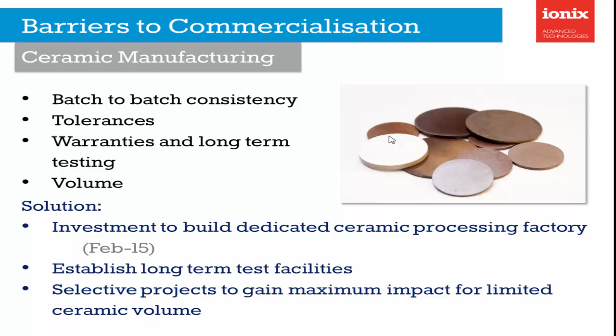Long-term testing is key. If you want to do some quick testing at 300 degrees centigrade for 10 minutes, you can do that with PZT - people are using PZT much hotter than perhaps everyone realises. But if you want a sensor sat on an oil pipe looking at a weld, and you want it to work for 10 years, you're going to have to prove it's up to the job. The only way to do that is to get stuff under test for long periods of time.